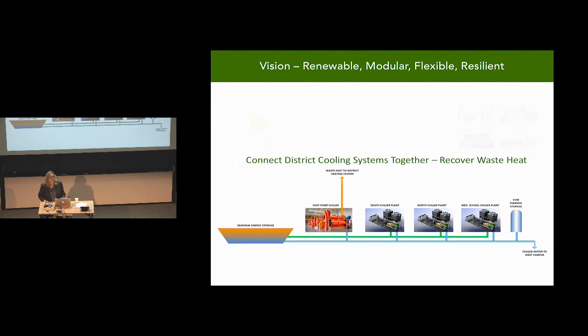By interconnecting those plants together, it will allow us to operate those systems as an integrated system, which will have a lot of advantages. Number one, it means that we can use the capacity we already have to serve future cooling loads on the campus, for example new buildings or renovations to existing buildings. It would also allow us to operate the system overall more efficiently by deploying the most efficient resources we have to meet those cooling loads.